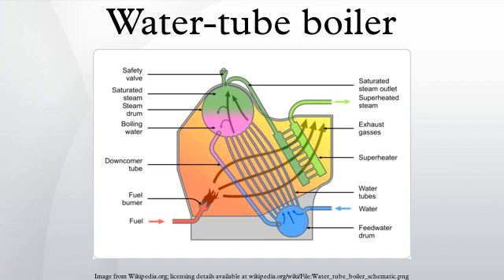Thornycroft: These tubes, especially the central set, have sharp curves. Apart from obvious difficulties in cleaning them, this may also give rise to bending forces as the tubes warm up, tending to pull them loose from the tube plate and creating a leak.